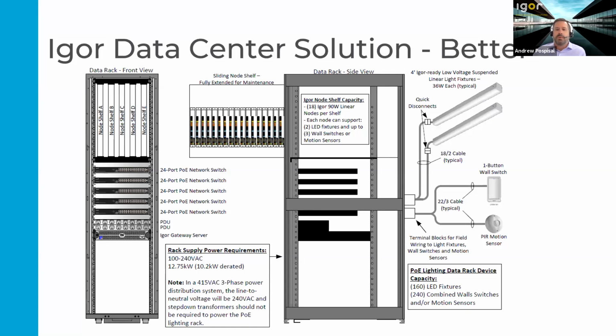and with some 18/2 cable running from some terminal blocks on the back of the rack out to those fixtures. And one of the advantages of PoE and the Igor solution is that those cables don't need to be run in conduit. This is all low voltage based power for the lighting. So these can be run right in the cable trays, which every data center has a ton of, going all over the place.